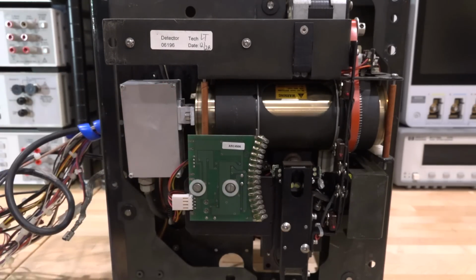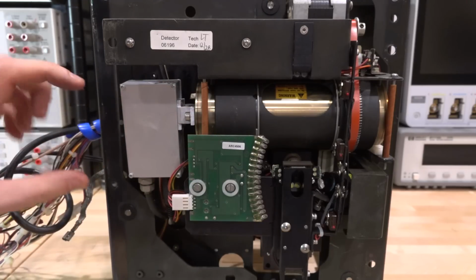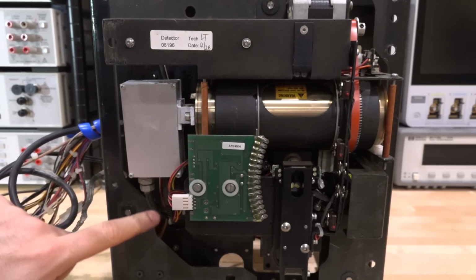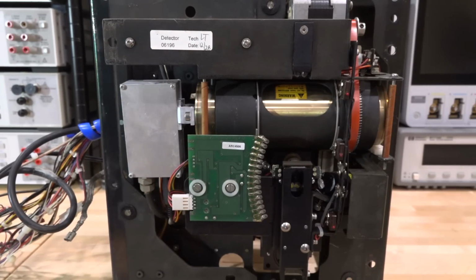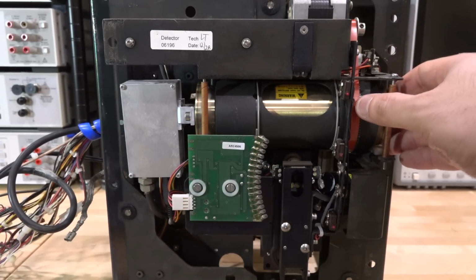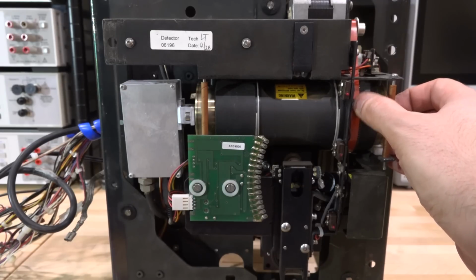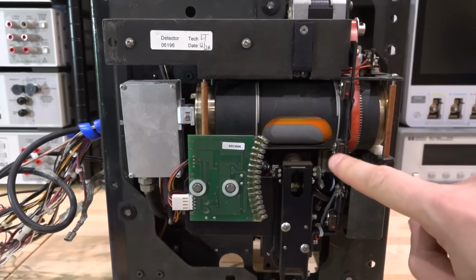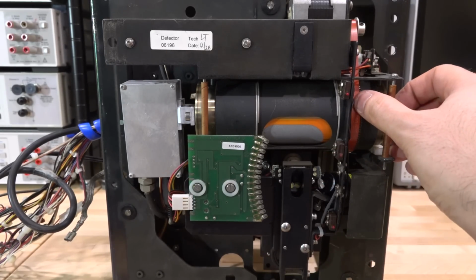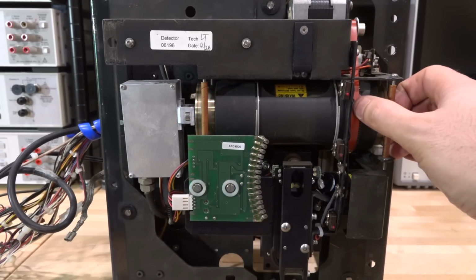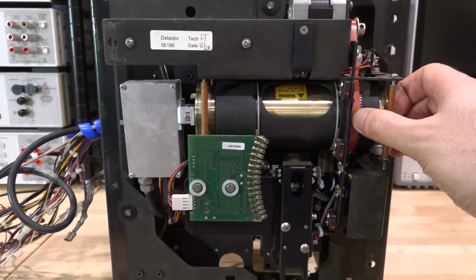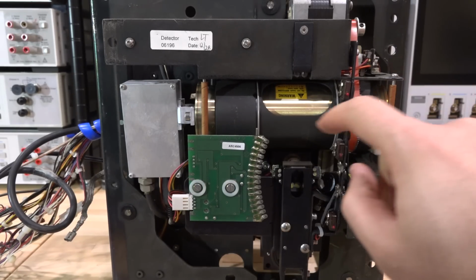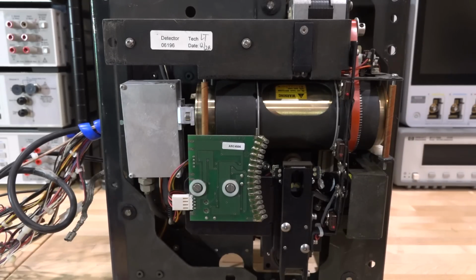Here's our detector, and I was mistaken. That cable actually goes into this detector in this box, the preamp or whatever it is that's inside of this. And there is a stepper motor up here that opens the window to the detector, and there's an interlock switch on that too. If I turn it, you can see the beryllium window right there. You're never supposed to touch that with your hand, of course. And then if you go over there, this actually closes it. There's a switch that tells you that you've reached the closure. Different openings can have different filters on it. I don't see any filters in this, which is interesting. X-ray filters, I mean. But that opens, basically allows the detector to start collecting data.